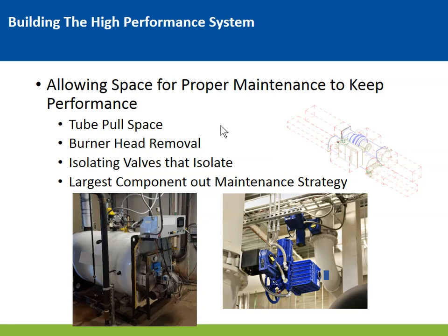Another thing that's pretty important in our industry is that isolating valves - you want to get an isolating valve that isolates over the life of the equipment. This is my opinion, but the rubber-seated butterflies of the industry today, I'd consider them good for about 10 years, and then they're going to start causing problems. So if you need that to run and isolate for 20 years, you might consider something better.